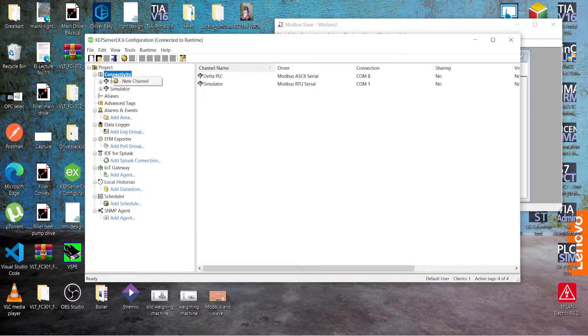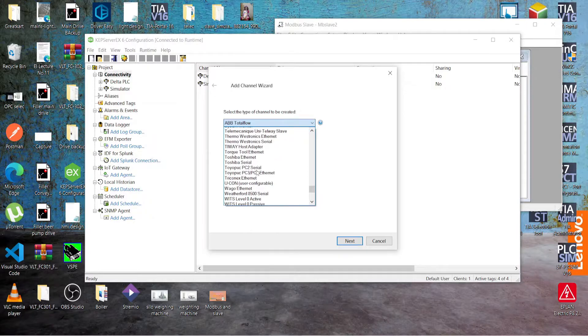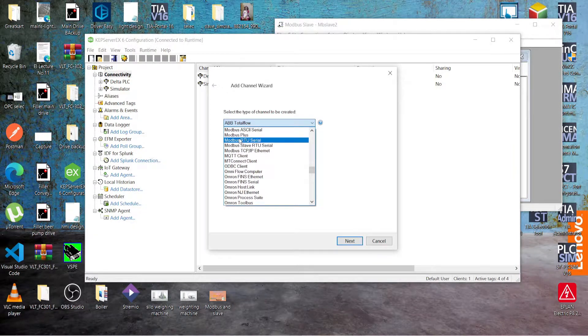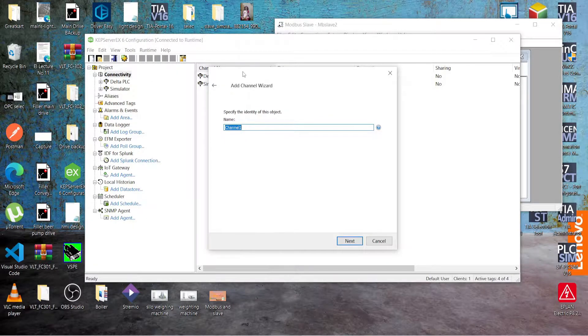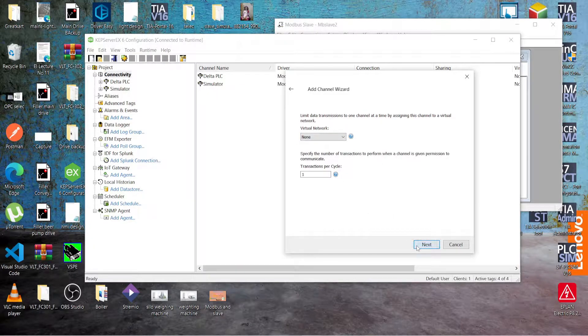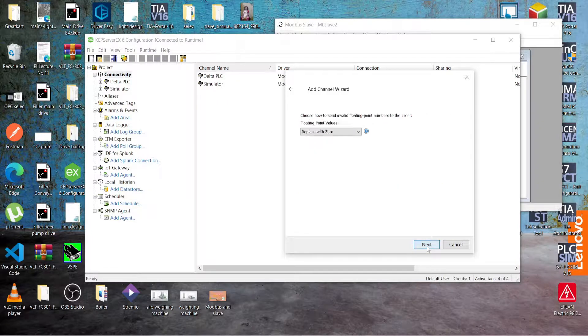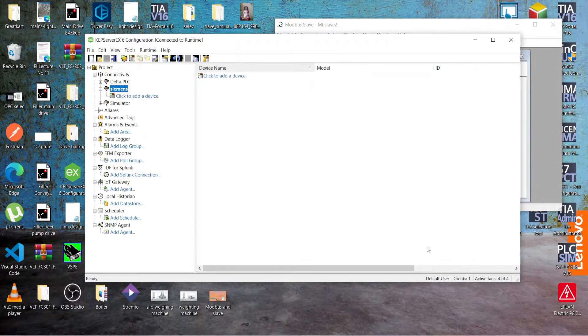You can add another channel. Go for Modbus RTU serial. For the next channel, whatever name you give — I already used 'simulator', but you can give any name as per your requirement. I'll use 'Siemens'. For the COM port, you have to go for COM 1, as this is connected to COM ID 1. Keep pressing Next until you finish, and then you can create the device.